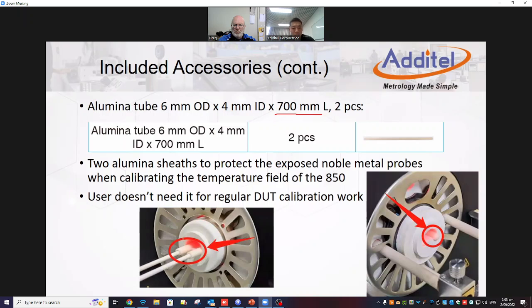So with this tube, one side is on the left side of the furnace, and the other side we can definitely put outside to the right side of the furnace. This can make sure that the reference probe is hanging in the middle of the furnace. The customer may use this the first time they receive the furnace, because we have a lot of vibration and shock during transportation, so we do recommend the customers do a temperature field testing once they receive the furnace, to test the entire performance of it.